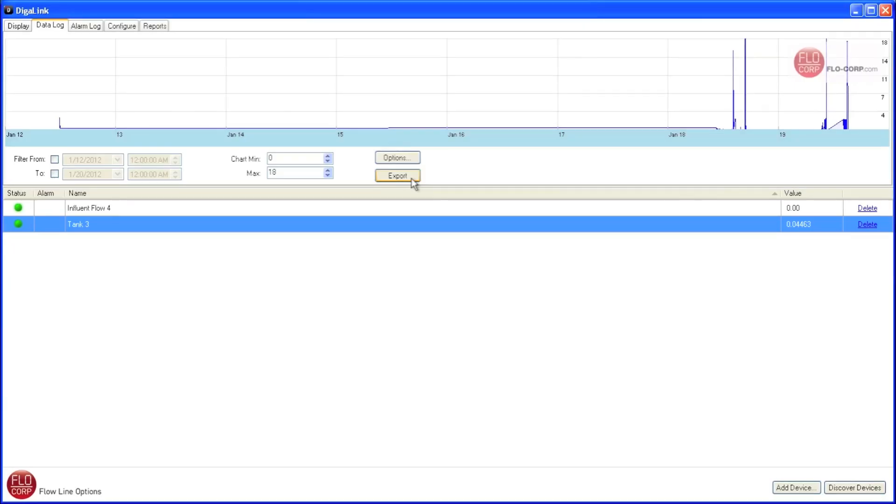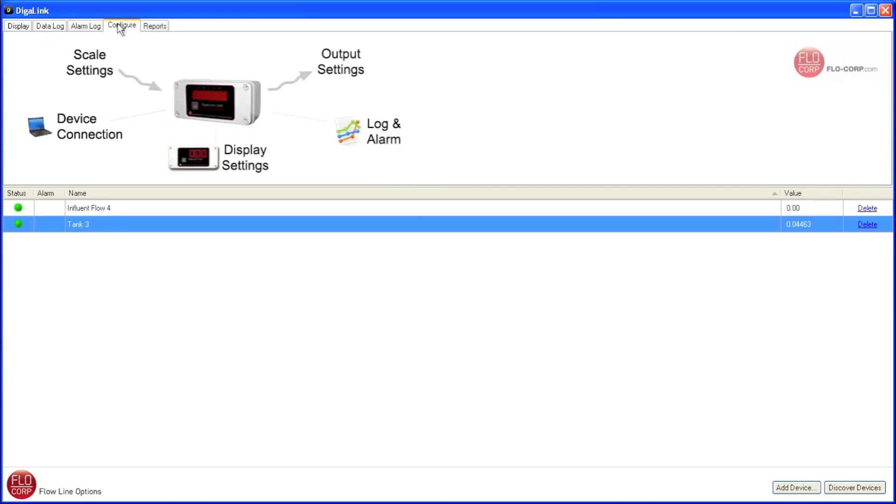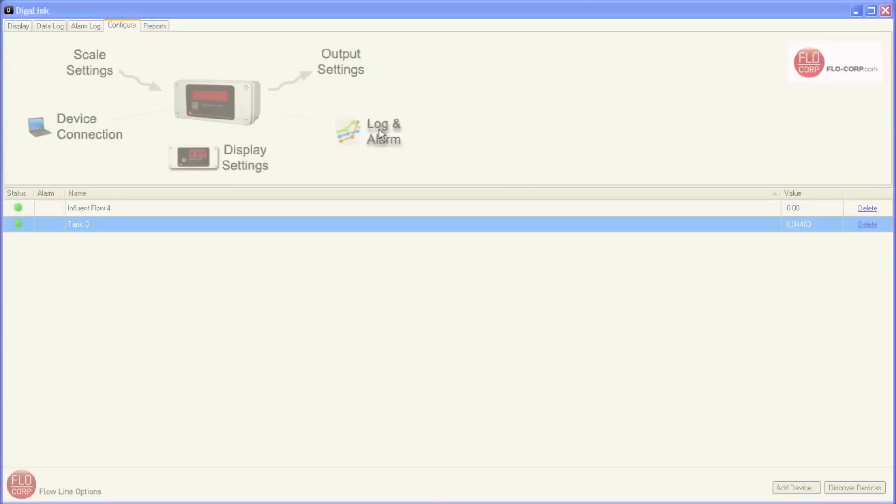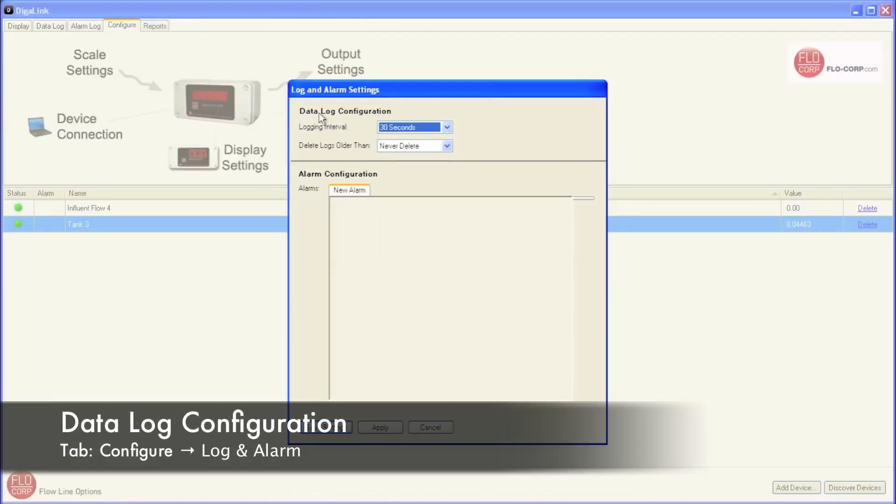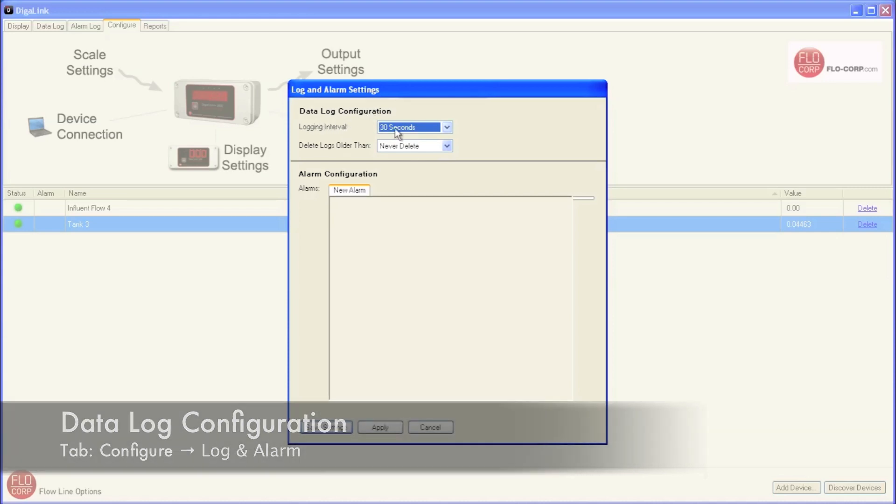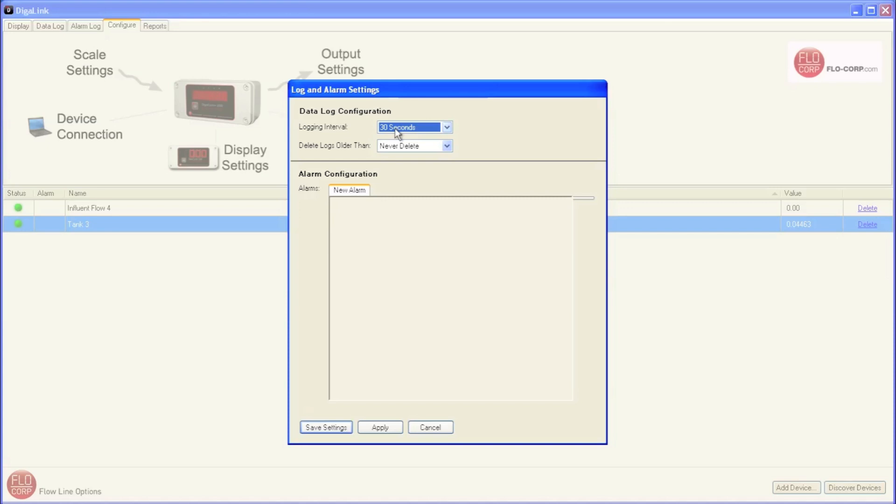The next tab we're going to take a look at is the configure tab. So let's move over a couple tabs to configure and click on that. And we're going to touch on several of the options on this screen, starting with log and alarm. When we open the log and alarm settings, we see data log configuration. And the current logging interval is set for every 30 seconds. So that's why when I put my fingers on the probe, we didn't instantly see that log in the chart. But rather, if I had held my finger there for 30 seconds, we would have seen it on the chart.